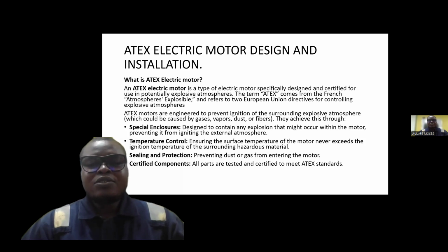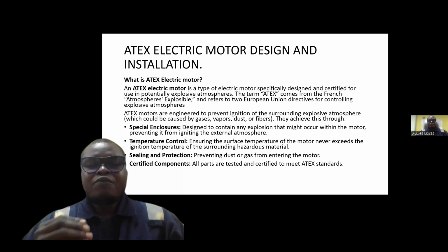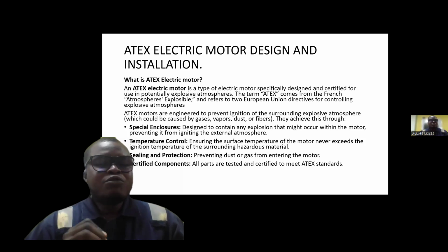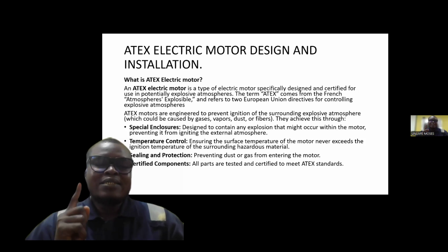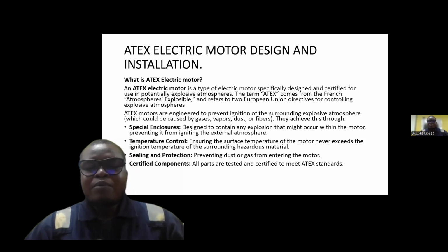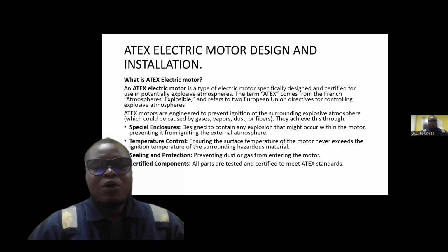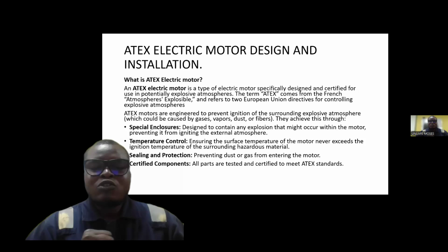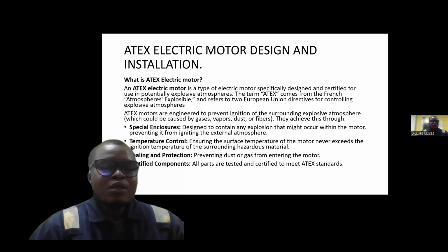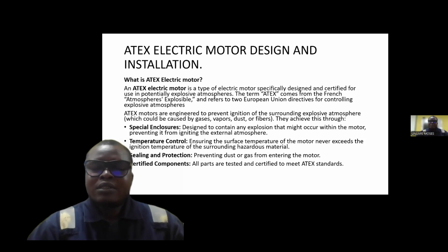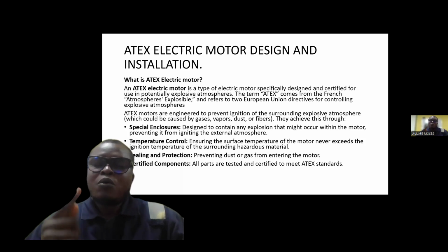Atex motors are engineered to prevent ignition of the surrounding explosive atmosphere, which could be caused by gases, vapor, dust, and fibers. They achieve this through special enclosures, which means designed to contain any explosion that might occur within the motor, preventing it from igniting the external atmosphere. And also temperature control, which means ensuring the surface temperature of the motor never exceeds the ignition temperature of the surrounding hazardous material. And also by sealing and protection, that means preventing dust or gas from entering the motor. And above all, certified components, that means all parts are tested and certified to meet Atex standards.